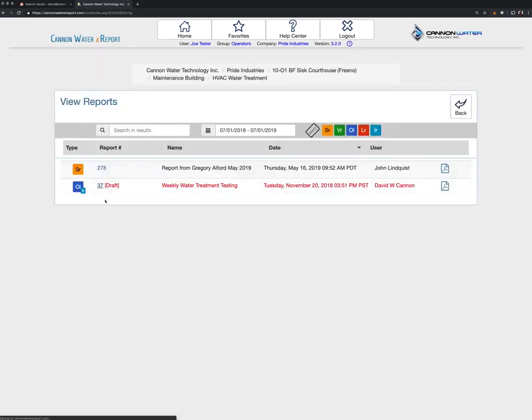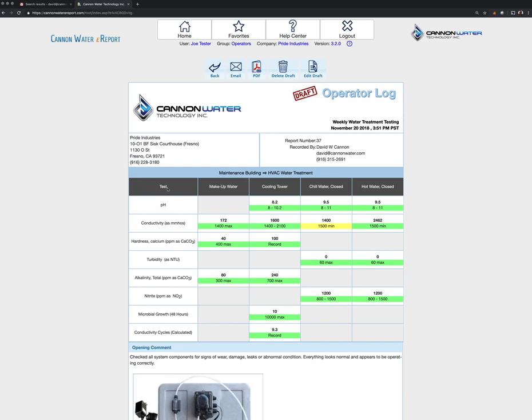Let's look at a past report that has some history on it. In this report, we have some parameters set for the various systems that are in place at this location. We have pH, and it's broken down into the test type and then the system or component that we're testing for. In this case, we have makeup water, we have a cooling tower, we have a chilled water loop, and we have a hot water loop in this building that we're recording parameters on. We can add or subtract from this list whatever systems you have. If you don't see the test that you're currently running, just get a hold of one of us here at Cannon Water Technology, and we will add those tests or train or change the parameters and setpoints for those particular tests. If we have to adjust a range, we can easily do that in the back end of the system.